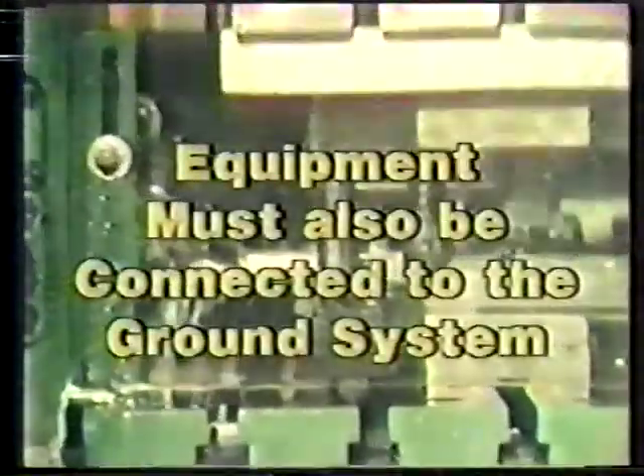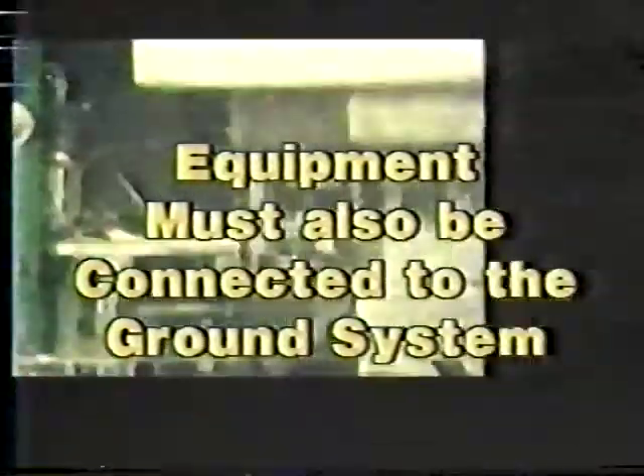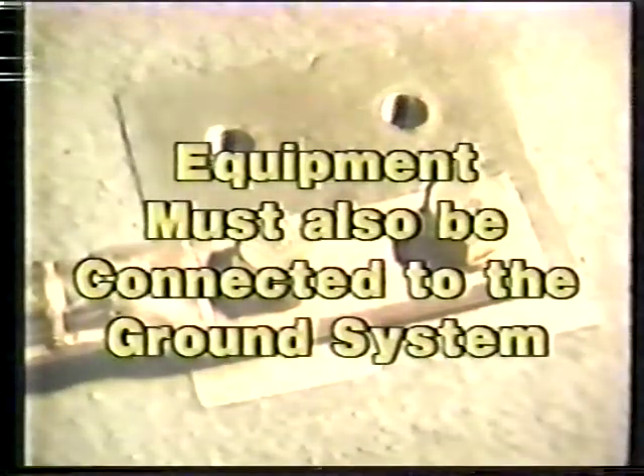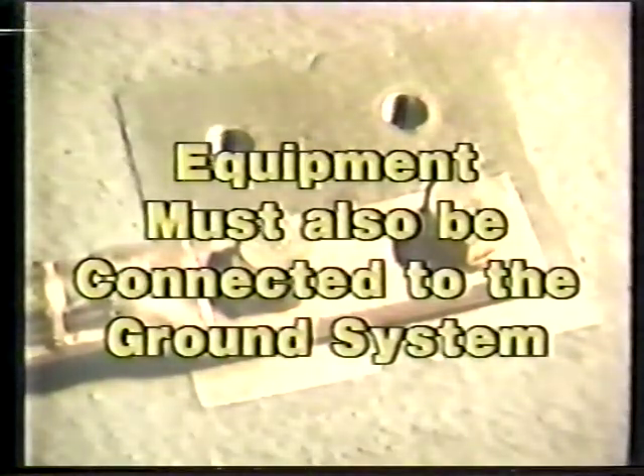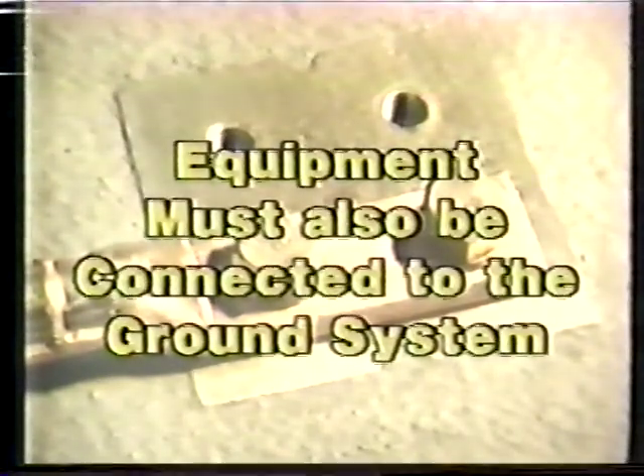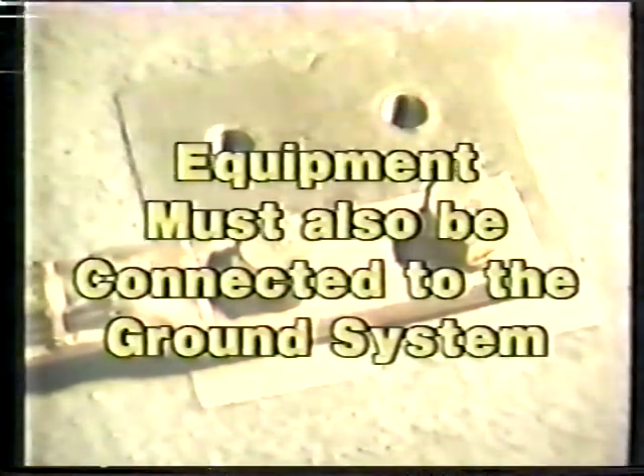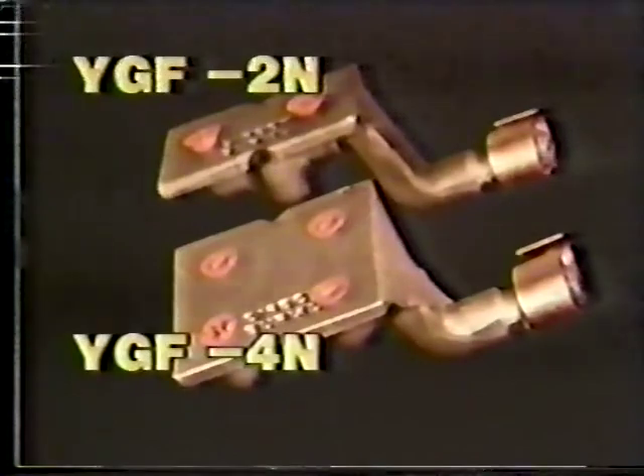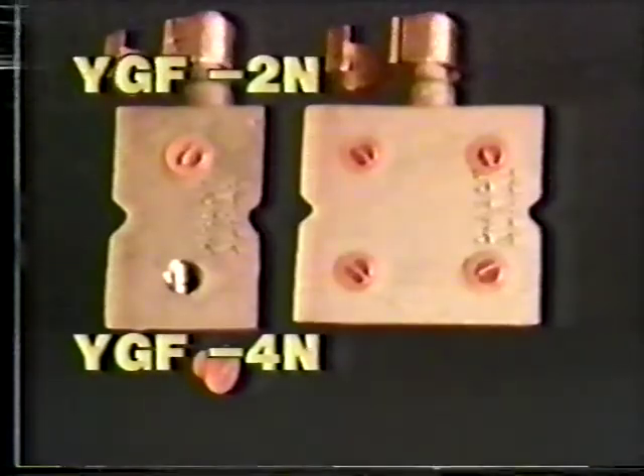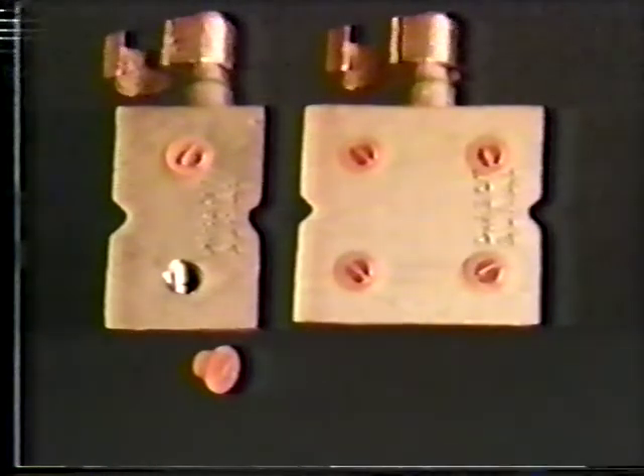For safe, efficient operation, transformers, generators, motor windings, and other equipment must be effectively connected to the grounding system. To meet this requirement, the Burndy Hyground system provides ground plates in both 2- and 4-hole NEMA-drilled versions. In addition, the tapped holes are plugged to protect them from damage or filling up with concrete during installation.